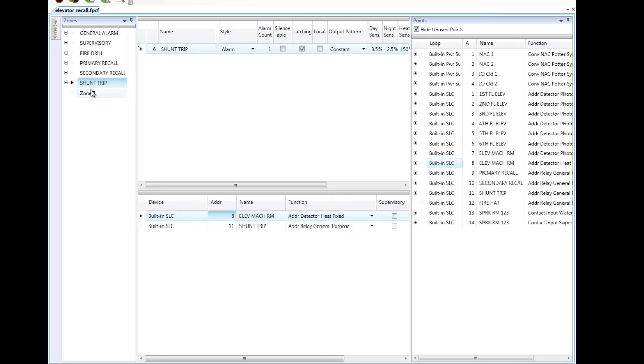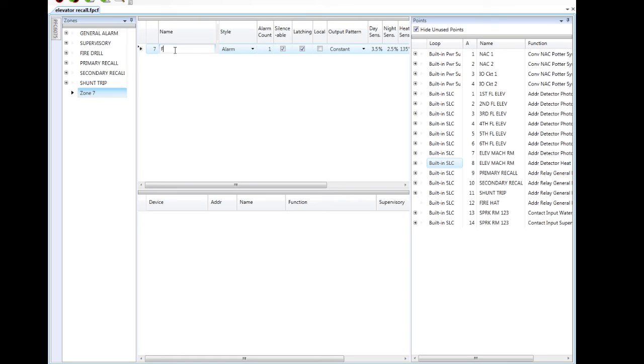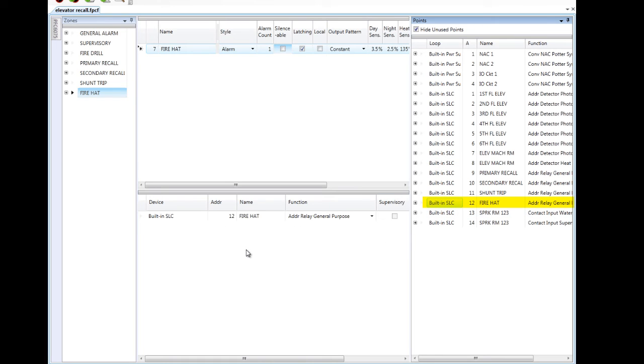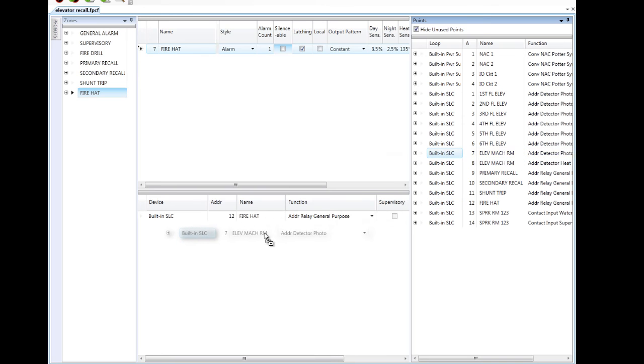My last zone for elevator recall is going to be my fire hat. Again, I'm going to make this non-silenceable. I'm going to grab the output — this is the relay that will trigger the fire hat. The fire hat is located in the elevator car, and this is triggered by the smoke detector in the elevator machine room. This is a tool for the fire department to know that the incident is now occurring in the elevator machine room. And those are the four zones for elevator recall.